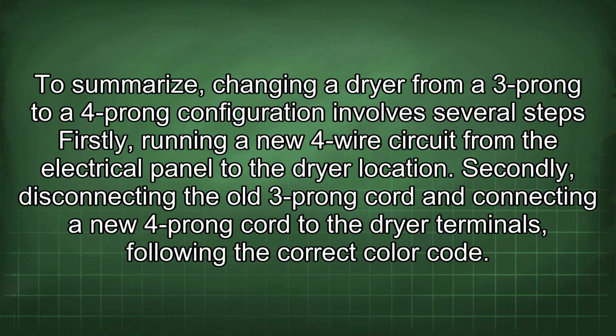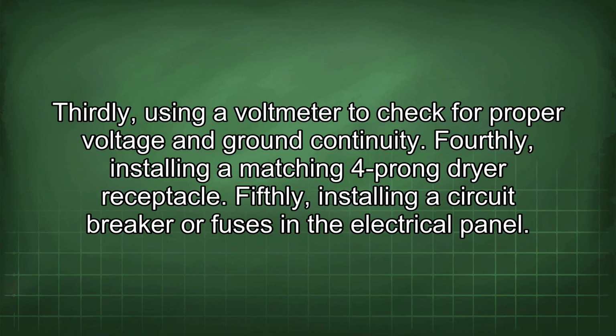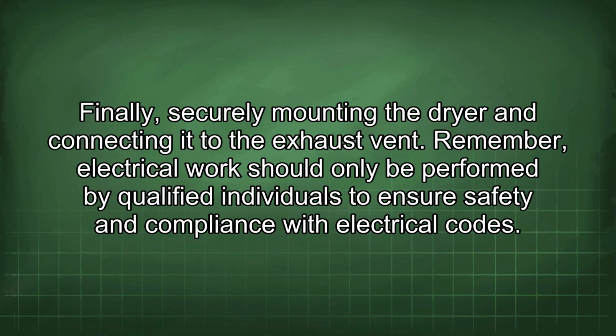To summarize, changing a dryer from a 3-prong to a 4-prong configuration involves several steps. Firstly, running a new 4-wire circuit from the electrical panel to the dryer location. Secondly, disconnecting the old 3-prong cord and connecting a new 4-prong cord to the dryer terminals, following the correct color code. Thirdly, using a voltmeter to check for proper voltage and ground continuity. Fourthly, installing a matching 4-prong dryer receptacle. Fifthly, installing a circuit breaker or fuses in the electrical panel. Finally, securely mounting the dryer and connecting it to the exhaust vent. Remember, electrical work should only be performed by qualified individuals to ensure safety and compliance with electrical codes.